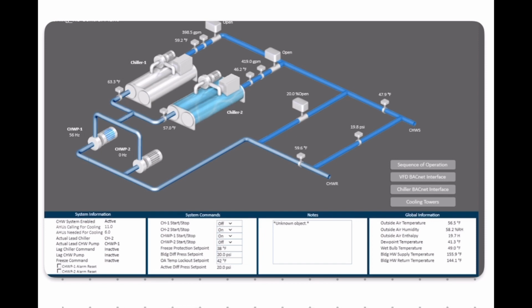So we got chiller number 2 running, and this is where your water goes in, your chill water. And I'm gonna explain to you how the water will run through this system. Again, this is the chill water side, not the condensing side yet. So we got chiller number 2 running, and then pump number 1 running. This will put your water into your evaporator side. In this case, we're talking about the evaporator in that tank that I circled. That's where your evaporator is, and that's how you cool down your water.